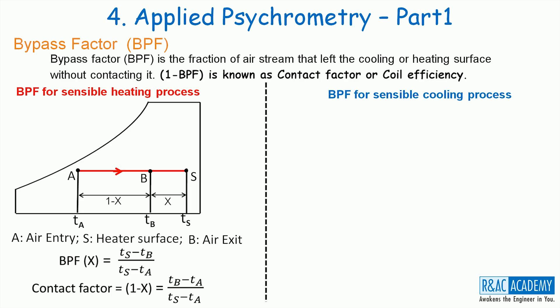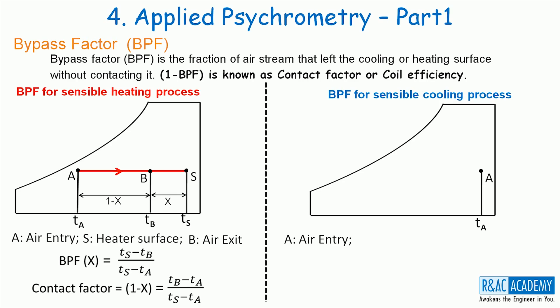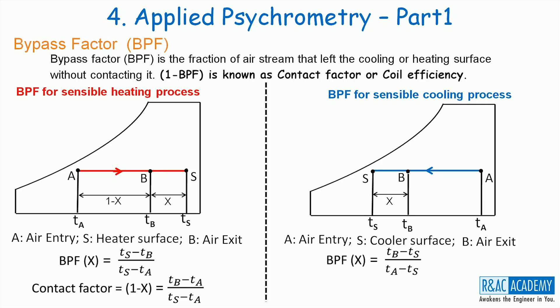For the sensible cooling process, let A be the state of air entering the cooling coil and S be the cooler surface. If all air contacts the cooler surface, the exit state would be S; but practically some air always bypasses the coil, so exit state B lies between A and S. The bypass factor for sensible cooling = (TB − TS) / (TA − TS), and the contact factor (1 − X) = (TA − TB) / (TA − TS).